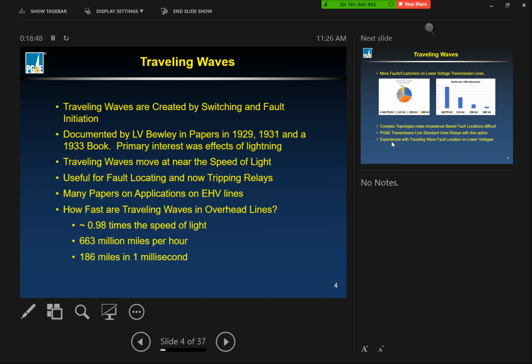So let's see. There have been many papers on applying traveling waves or fault location on EHV lines, which is a term for extra high voltage. So like 500 kV, 765 kV lines, 345 kV lines. Those lines tend to be what we call a clean line with no taps, one wire size, similar construction. Fault locating is great on those lines, but those lines don't have as many faults. And traditional impedance-based methods of determining fault location tend to work pretty well. So we'll talk about fault rates at different voltages on transmission lines, and the different topology or configurations of different voltages.